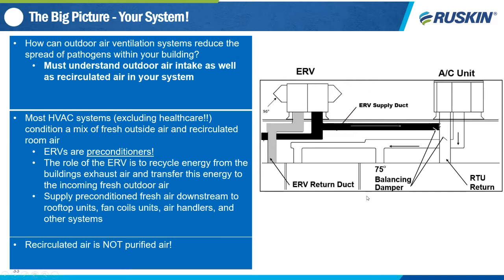Then you see the ERV supply exceeding, in this case, we have a rooftop unit, the RTU return. So the ERV is a preconditioner. The role of the ERV is to recycle energy from the building's exhaust air and transfer this energy to the incoming outdoor air. The ERV can reduce load on your system by up to 20%. So essentially, the ERV is preconditioning the outdoor air coming into your unit.